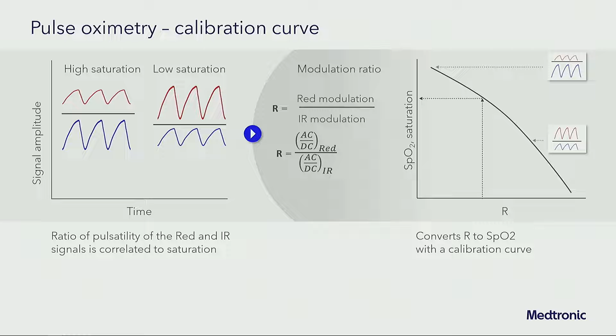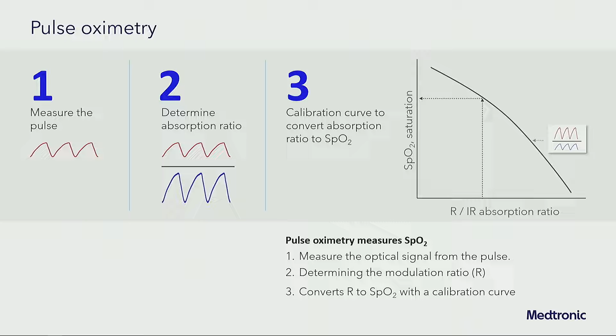And that has everything to do with the sensor itself and where it's supposed to go. And this is one of the reasons that you can't just move the sensor from a finger to an ear and expect it to be accurate, because all of the assumptions that are built into the technology to give you this calibration curve don't apply to different parts of the body. So you really have to be careful about using the right sensor for the right part of the body. Even if you can get a number, remember the assumptions are not being met, so you can't trust that number. So the way the pulse oximeter works is it's measuring the pulse, it's determining the absorption ratio, and then it's using that calibration curve to give you a SAT.